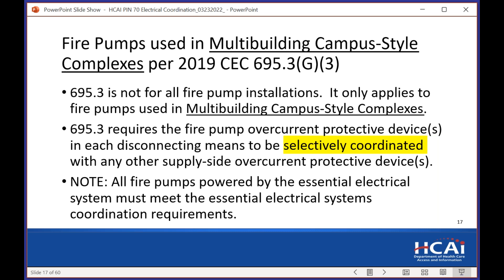Okay, so what they're talking about, a set of overcurrent protection devices: this is showing a circuit breaker, but you could have fuses, and you would have a set of fuses. You'd have 3 fuses here, one for your A, B, and C phase, but they work to protect this one secondary feeder. That's what the term set of overcurrent protection devices is talking about. Where here, if these were fuses, you'd have 3 fuses here, 3 fuses here, and 3 fuses here. 3 sets of overcurrent protection devices.